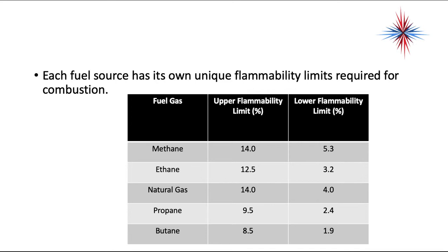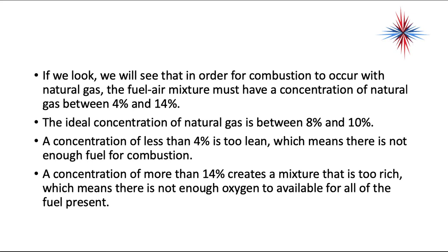Each fuel source has its own unique flammability limit required for combustion. For methane, 14% is as high as you can go and 5.3% is as low as you can go — anything outside these ranges, the fuel will not burn. For natural gas, the fuel-air mixture must have a concentration between 4 and 14%, with an ideal concentration between 8 and 10. A concentration of less than 4% is too lean — not enough fuel. A concentration of more than 14% is too rich — not enough oxygen for all of the fuel.